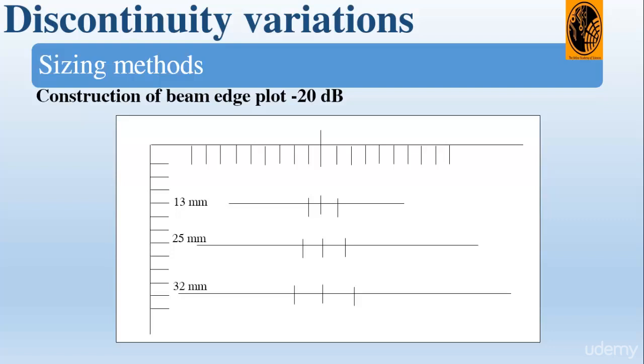We have marked the three positions for depths of 13 mm and 25 mm, and we can also do the same for 32 mm. For each block we have three positions: the center position where you get the maximum signal, the left side position at 10% signal, and the right side position at 10% signal, and so on.